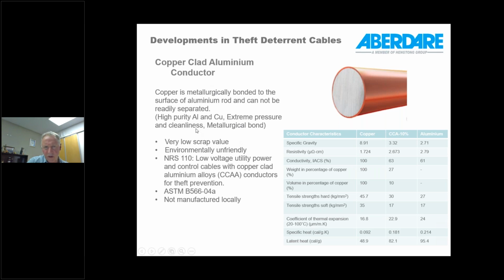This conductor also has a very low scrap value due to the dissimilar metals. It is seen to be environmentally unfriendly in that there's very little one can do with this metal. You can recycle, and there are some alloys which can be made with aluminium and copper, but those are very specialized alloys, so it will probably end up in a scrap bin somewhere. So it is really problematic. It's also difficult to manufacture and control within the manufacturing process. These conductors break easily. They also stretch easily, and are prone to high scrap rates in the manufacturing process.